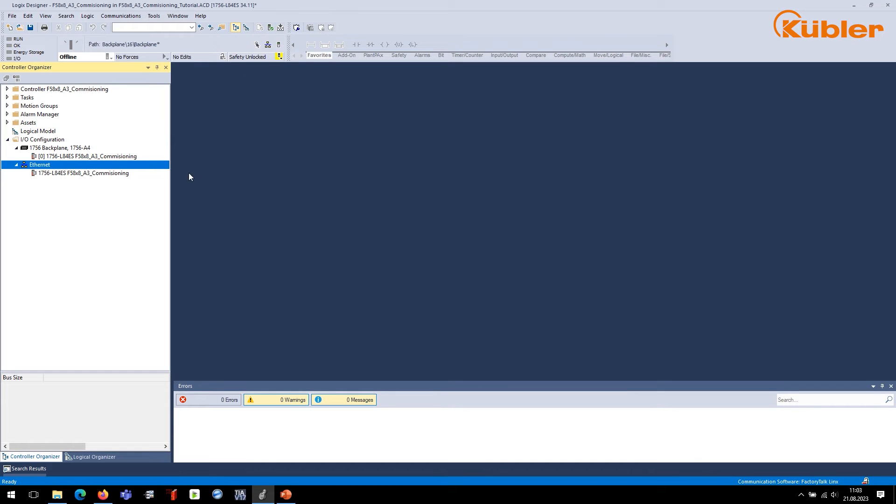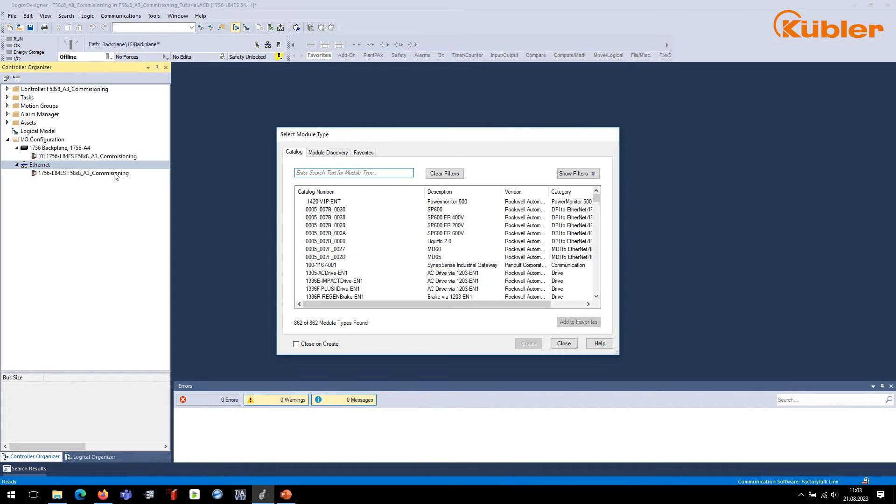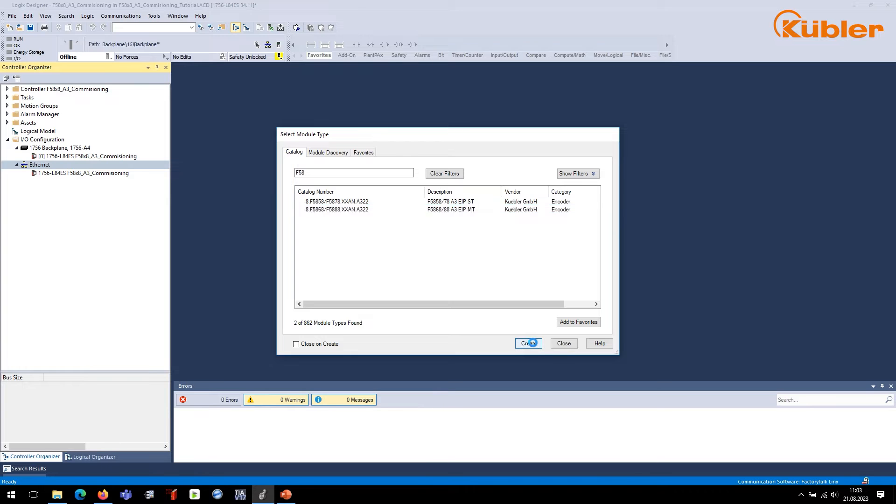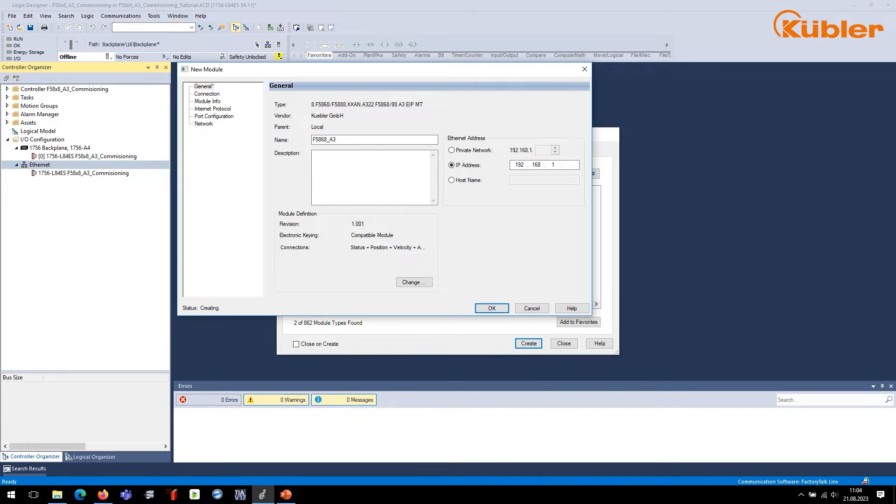In Logix Designer, go to IO Configuration and right-click on Ethernet. Choose New Module and search for the encoder name in the next window. Input the desired name of the new encoder, here F5868_A3, and its IP address. In our example, this is 192.168.1.30. In the Module window, click on Change.